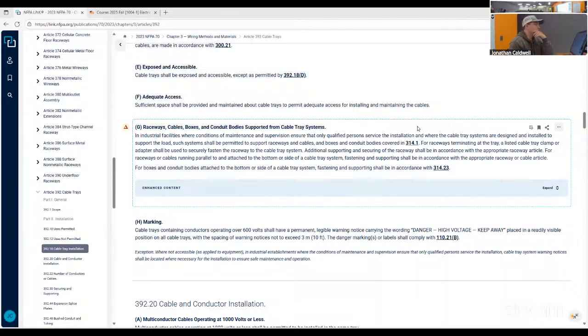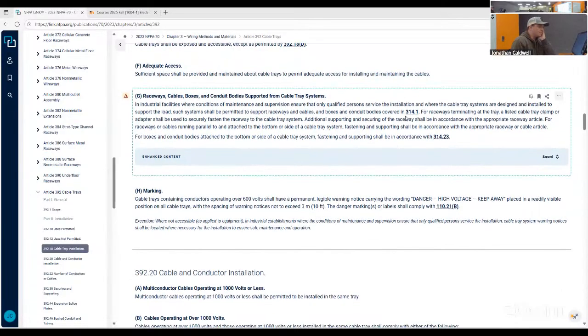And unless you are 100% supporting your cable tray, do not support anything on it. And what I mean by that is like out at Simplot right now, we literally have another contractor that is welding angle iron below our tray, and have angle iron trapeze pieces that support this. And the tray is 100% supported. Essentially they are building a metal cable tray underneath our cable tray to support it, it just doesn't have runs. So with that being said, that is now considered like a structural support. So now we can actually support off of that.